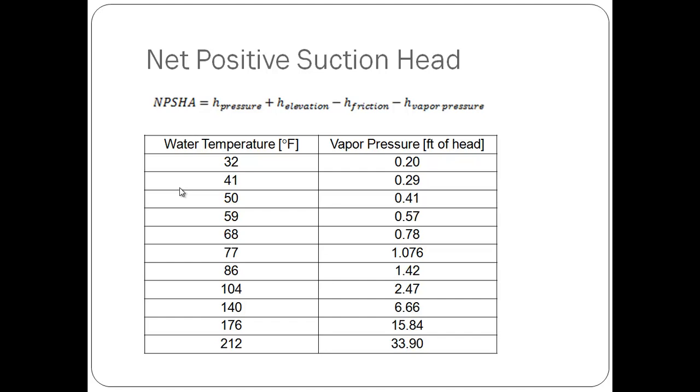and minus our vapor pressure. We find the value that corresponds with 86 degrees Fahrenheit as 1.42 feet of head.